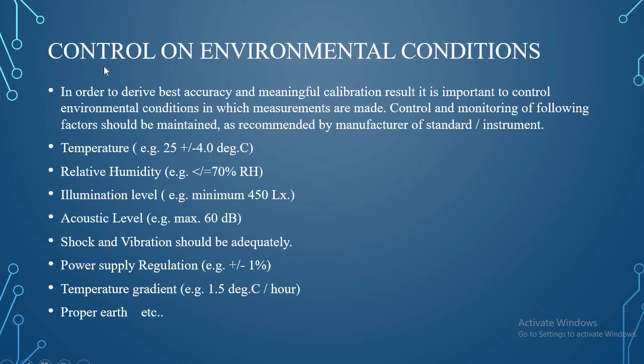So now, why is control of environmental conditions required while we make the calibration? In order to derive the best accuracy and meaningful calibration results, it is important to control the environmental conditions in which measurements are made. And control and monitoring of the following factors should be maintained as recommended by the manufacturer of the standard or instrument.